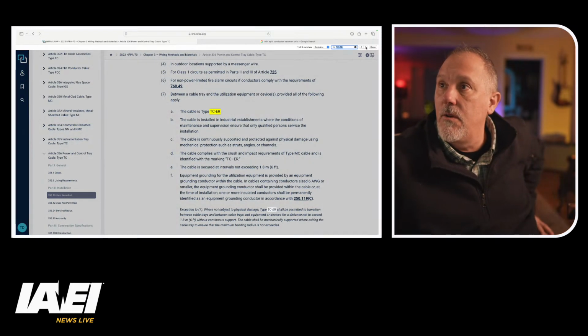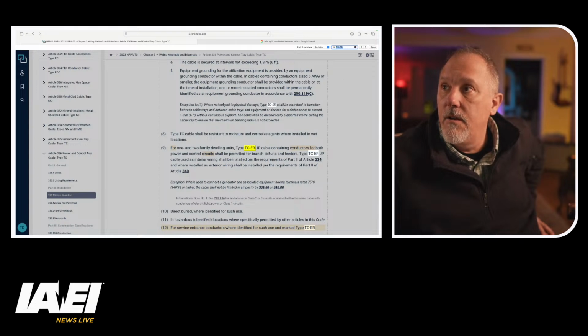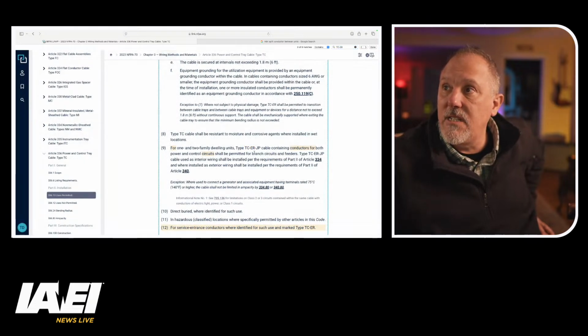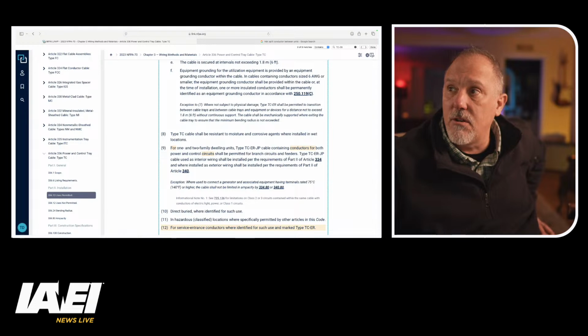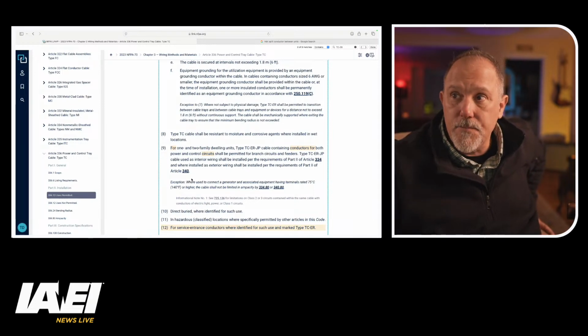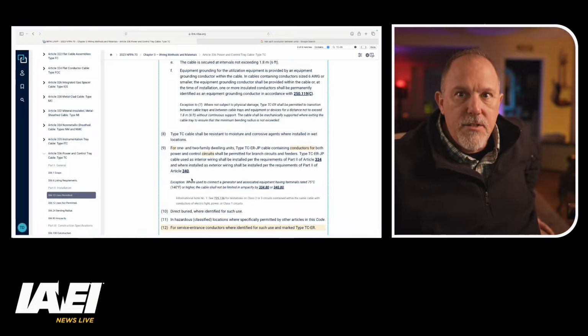So you could go to this article for 1 and 2 family dwelling units, type TC-ER-JP. Cable containing conductors for both power and control circuits shall be permitted for branch circuits and feeders. Type TC-ER-JP cable used as interior wiring shall be installed per the requirements in Part 2 of Article 334, and where installed as exterior wiring per Part 2 of Article 340. So there are provisions in Chapter 3 on how to properly apply TC-ER cable for those applications.